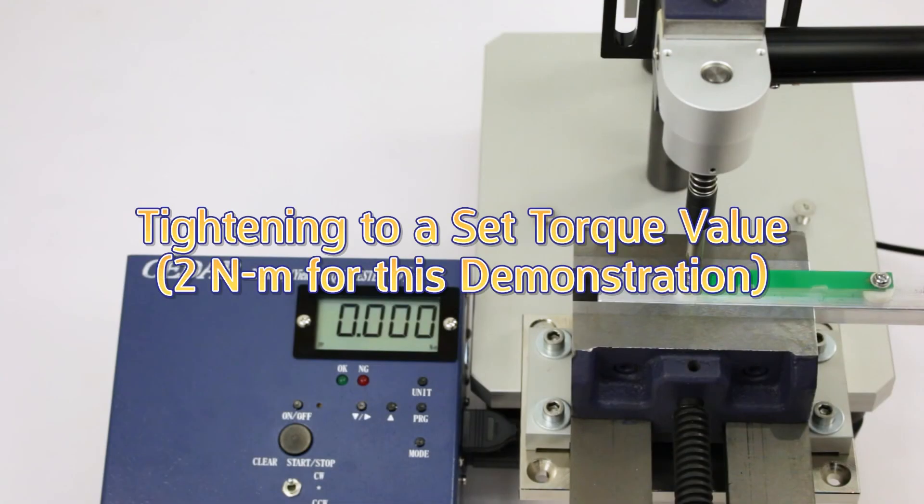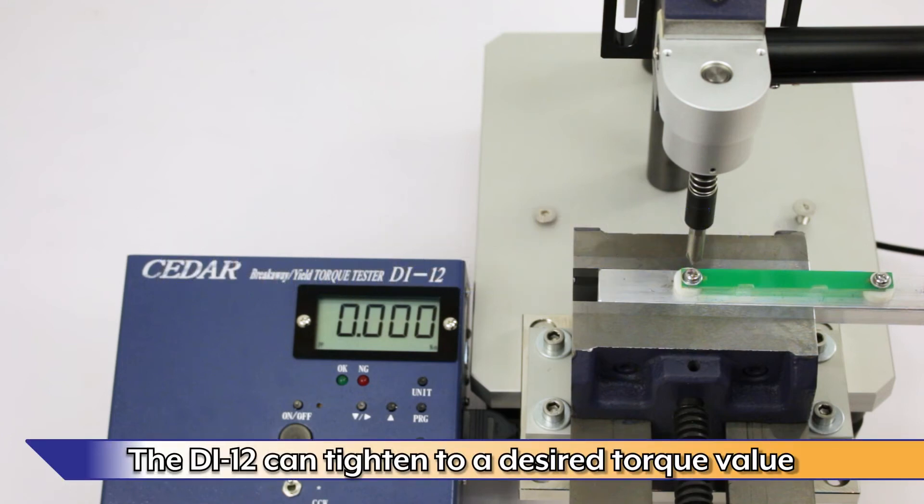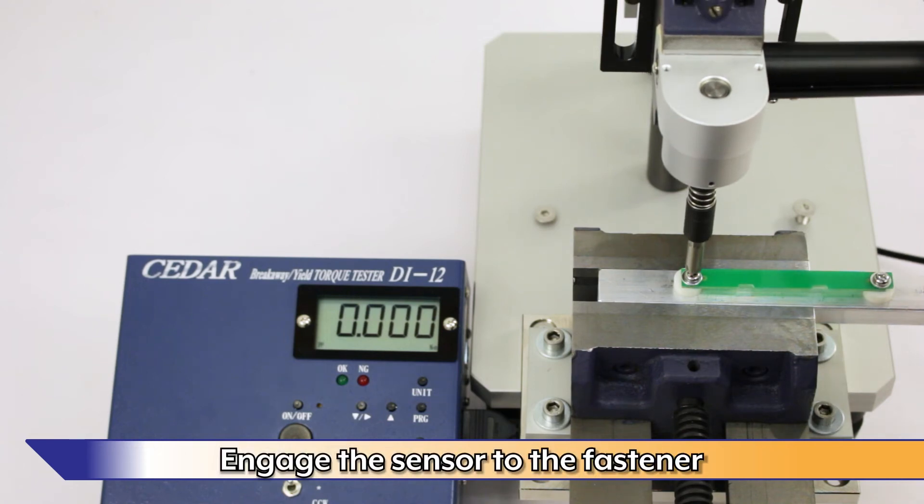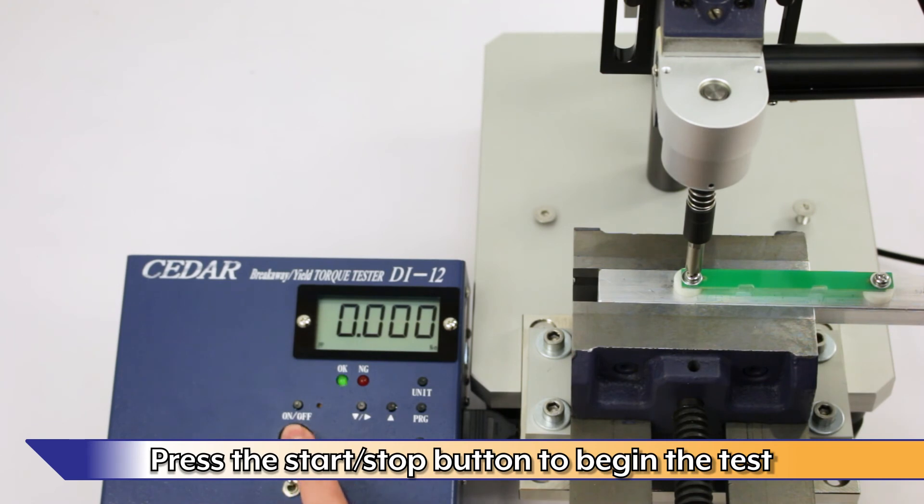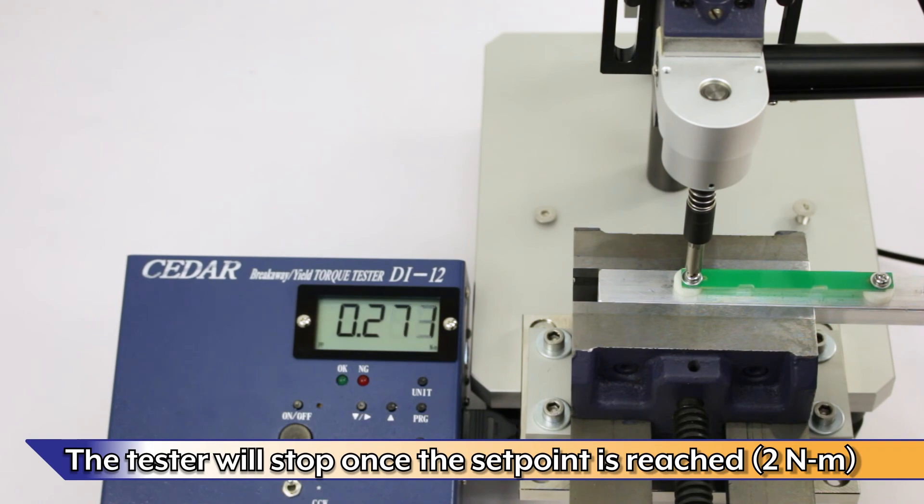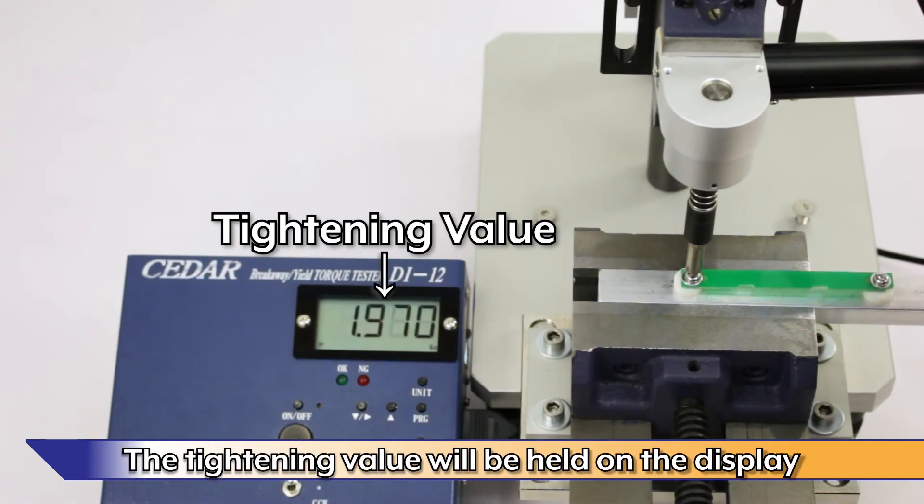Tightening to a set torque value, 2Nm for this demonstration. The DI-12 can also tighten to a desired torque value. Engage the sensor to the fastener. Press the Start-Stop button to begin the test. The tester will stop once the set point is reached, 2Nm. The tightening value will be held on the display.